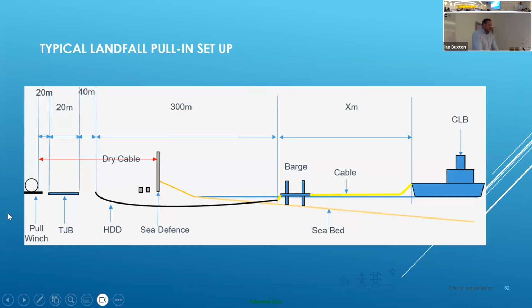It's a typical landfall setup: a pulling winch onshore, sea defence, cable lay vessel, and support barge, be it a jack up or spud leg barge. We position the support barge at the entrance to the HDD - lengths can vary between 50 to 1,500 meters. We've got a very high powered winch to pull the cable in, feeding it through the HDD onto the barge. The cable lay vessel feeds the cable from the vessel onto the barge, connects it to the pulling winch, and then commences pulling in from onshore.